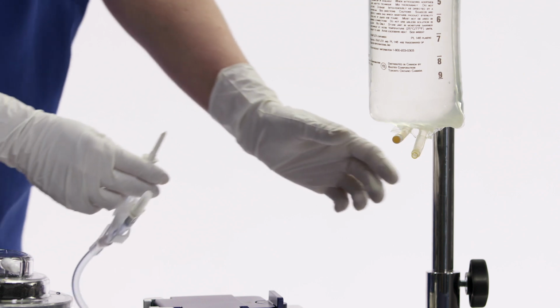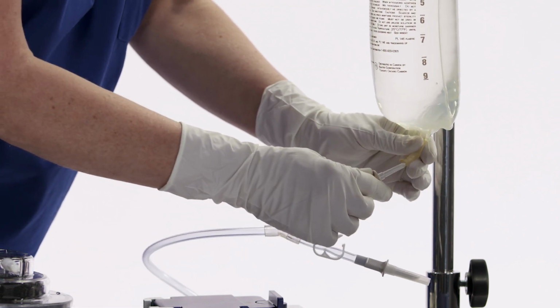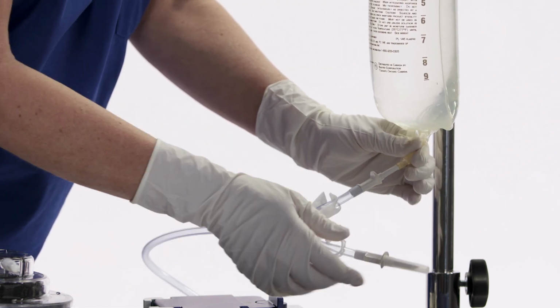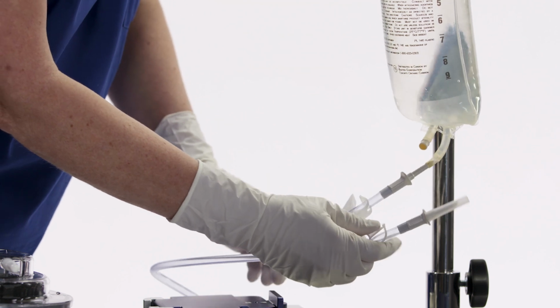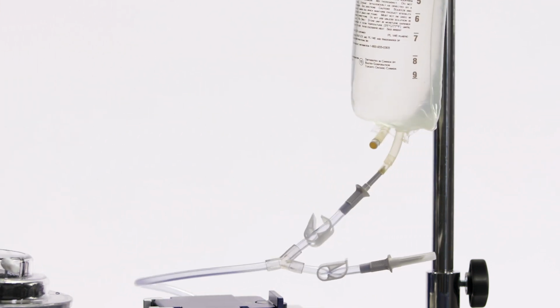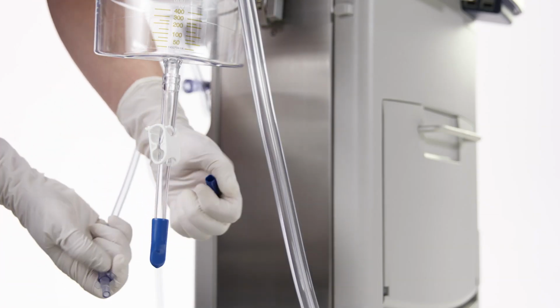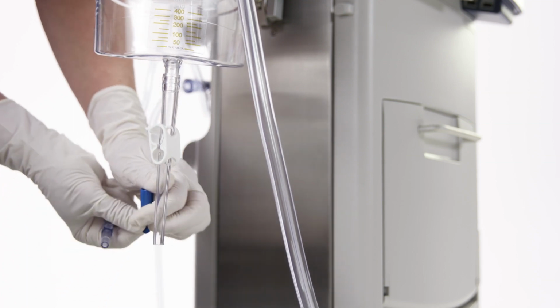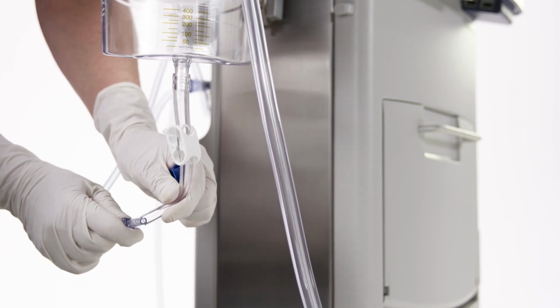Spike the middle manifold tubing into the saline bag or bags. If you're using just one bag, make sure the clamp on the unused saline line is closed. Now connect the left-hand tube of the manifold to the blue-capped step-down connector at the bottom of the collection reservoir and open the clamp on the connector.